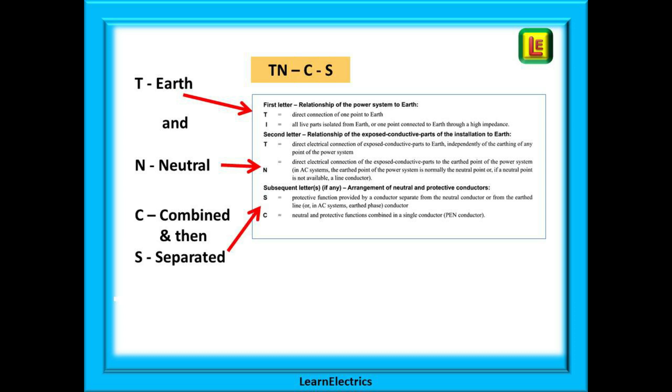Consider TNCS next. T for earth. N for neutral. C for combined. The earth and neutral share the same conductor. And then S for separated. At the intake position to the building, the earth and neutral are given their own conductors that are separate from each other. We now have earth and neutral are combined and then separated.